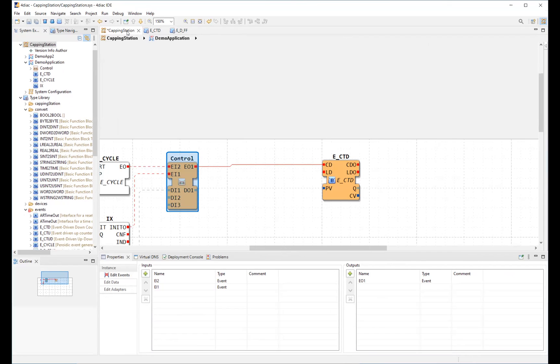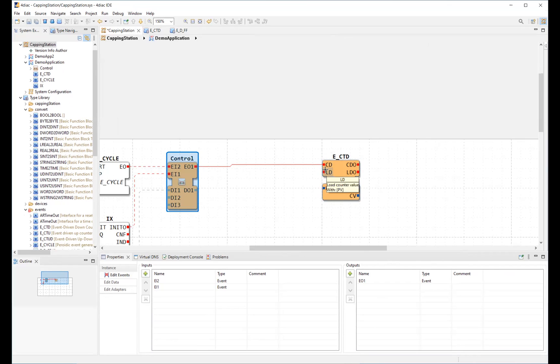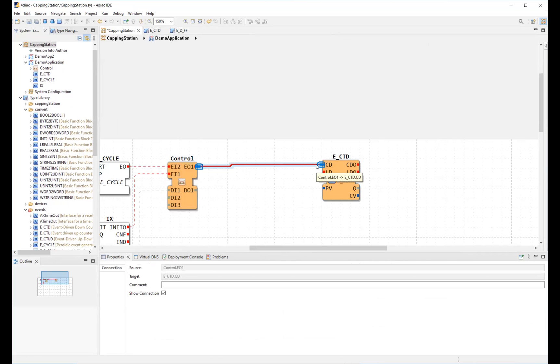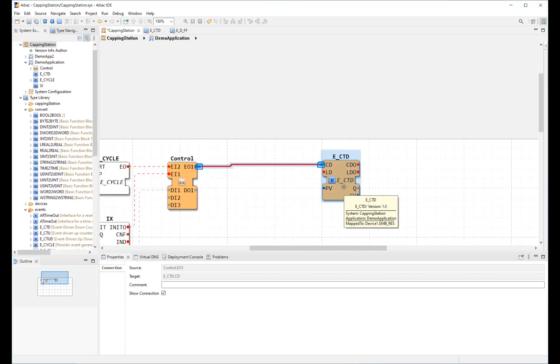Function blocks are fully encapsulated and they do not support global variables. They are only executed when a trigger arrives at the respective event input. They are the red pins. A function block has an interface with a variable number of inputs and outputs. There are event interface pins and data interface pins.